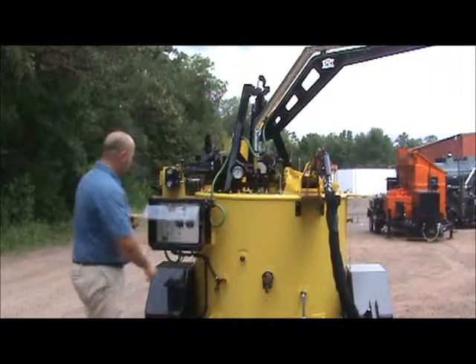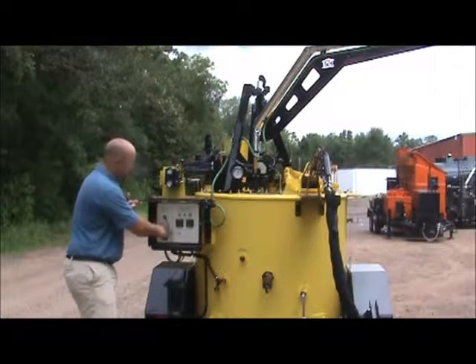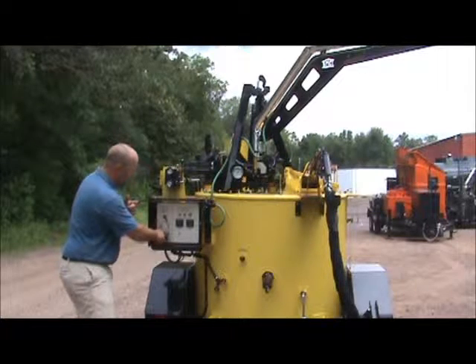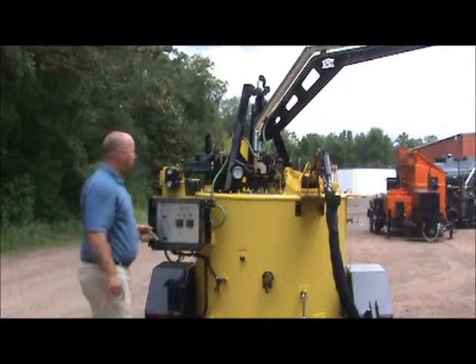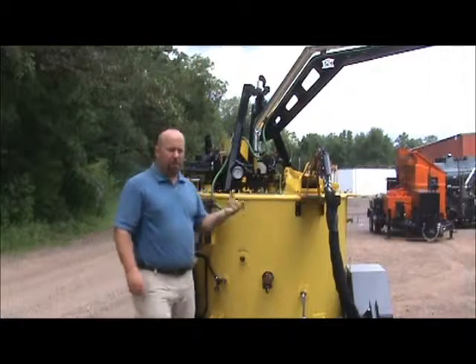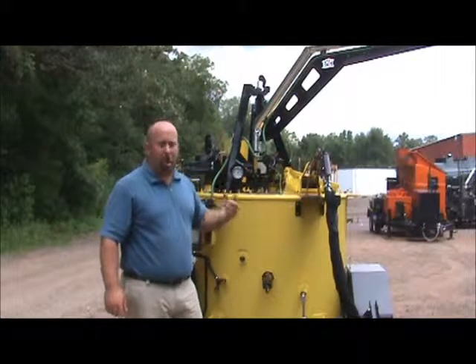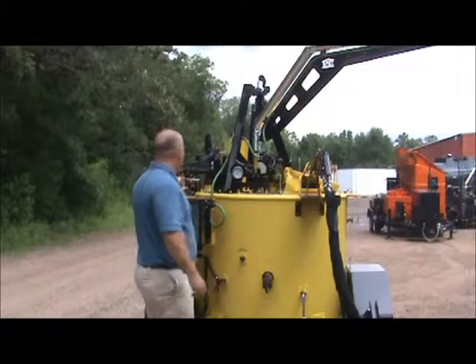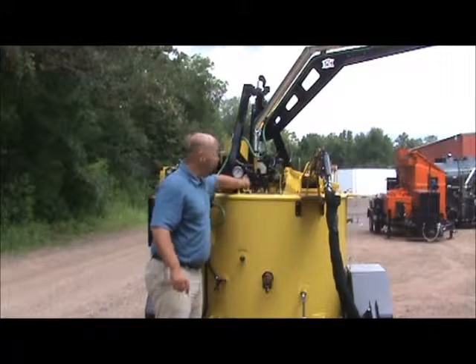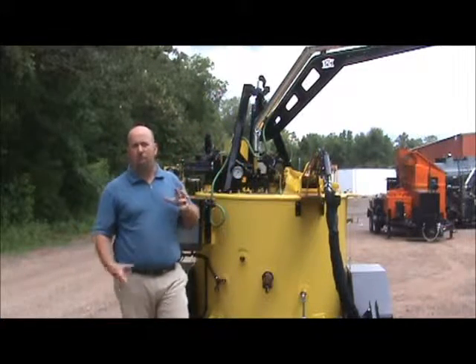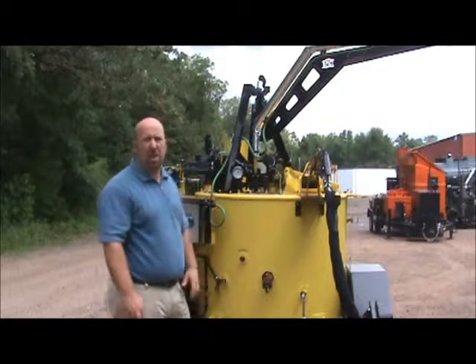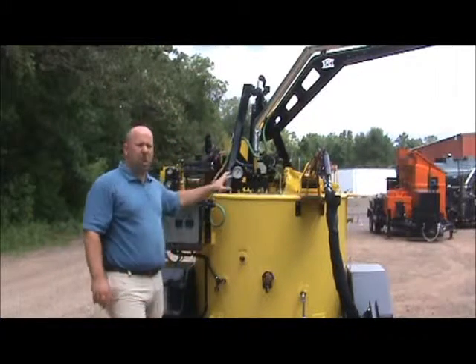We're going to come here and turn our pump in the reverse position. Turn our wand control off, or down to the pump saver. And we're going to reverse the pump for anywhere from 60 seconds to 3 minutes. What we're doing is evacuating this plumbing and getting the material out of the pump. That's just going to help your heat up times tomorrow morning, getting a flow established through there.